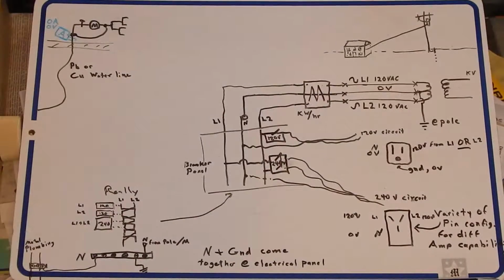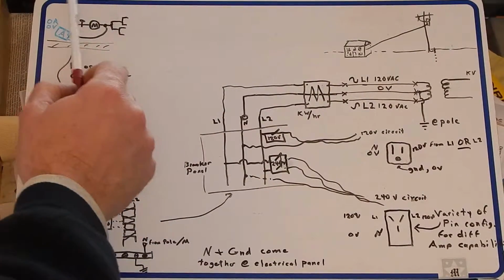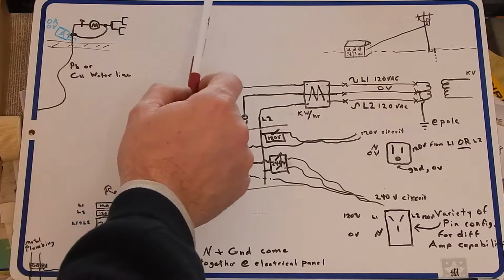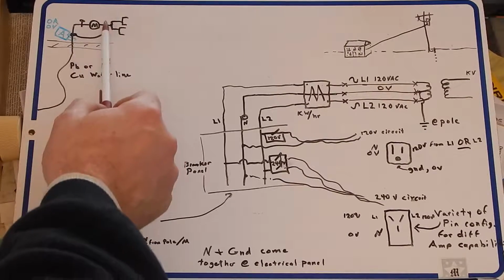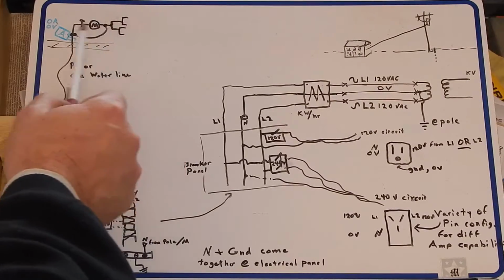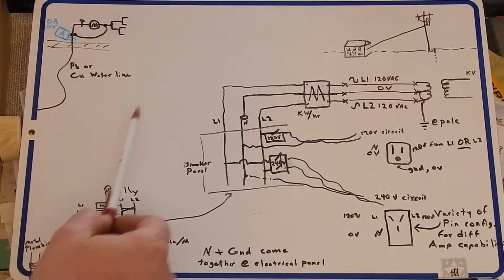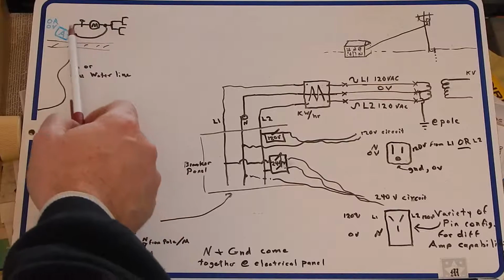And he's going to do a video, I wrote down here, much worse is when neutral from the pole fails. Very dangerous. Could have nearly 240 volts on half your outlets in an extreme case. Typically the lights are going bright dim. The cable TV or phone line might be smoking as the neutral current tries to find a path. Usually the water line ground takes the brunt of it, which is why the ground and the meter bypass ground are so important. You've got a ground wire going across your meter to prevent current from going through the meter, which is a casted bronze housing or something like that usually. Can't take the current too well. So they do a bypass.